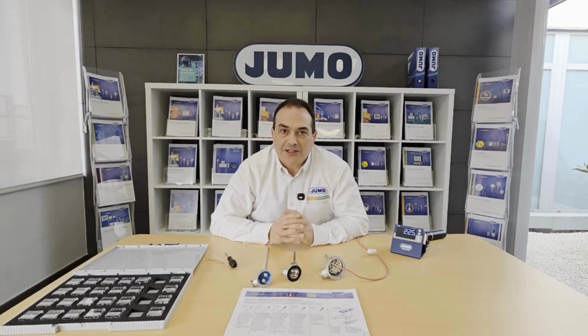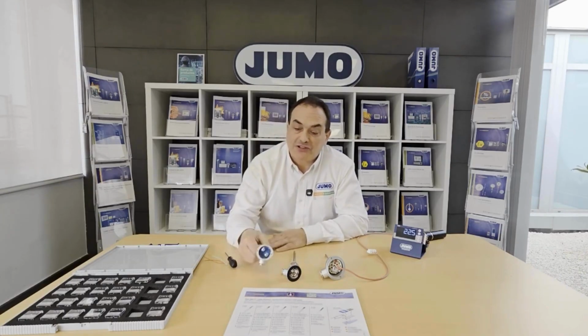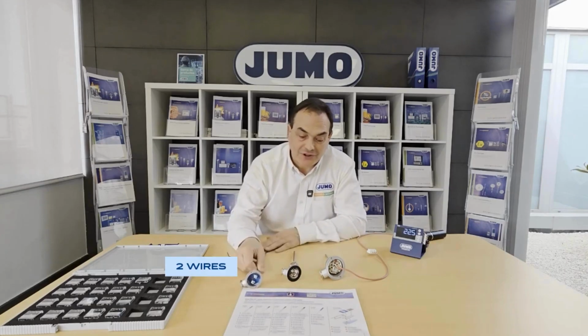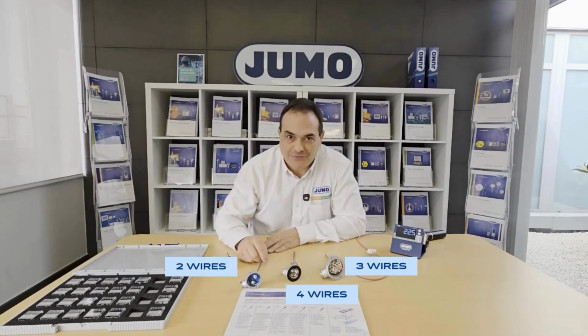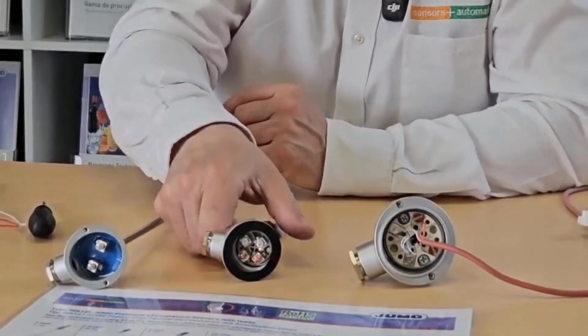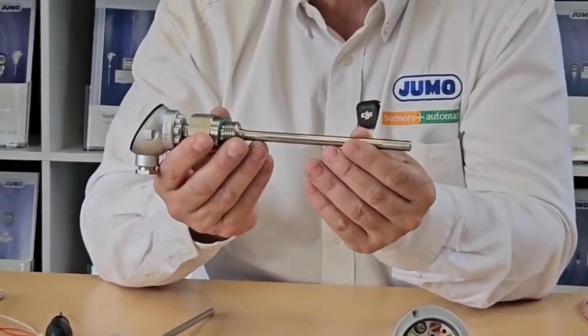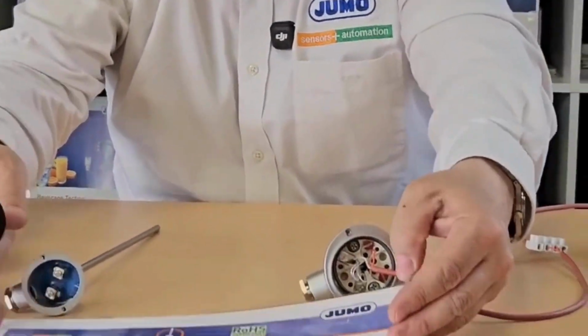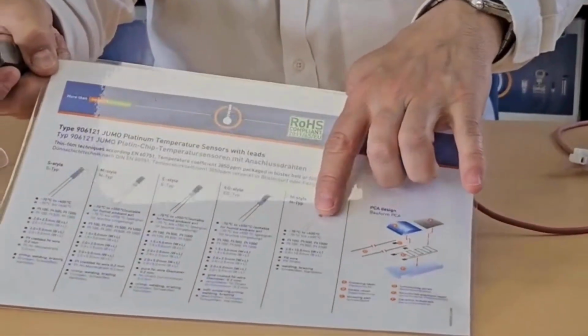When we talk about PT sensors, it's common to find in various catalogs, on Google and so on, that there are resistance thermometers or temperature sensors connected with 2 wires, 3 wires, or 4 wires. Actually, inside the sensor device, it's always the same. There's a chip at the tip, which, as you can see, has 2 pins. These are the ones I'll be wiring up.